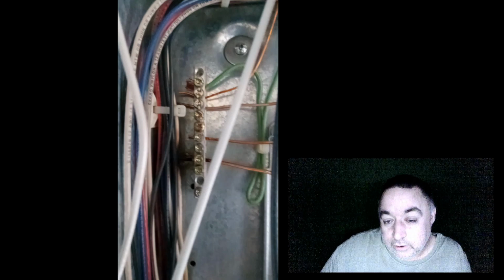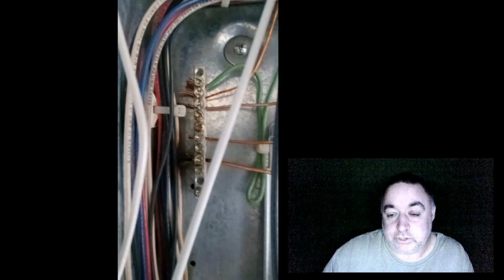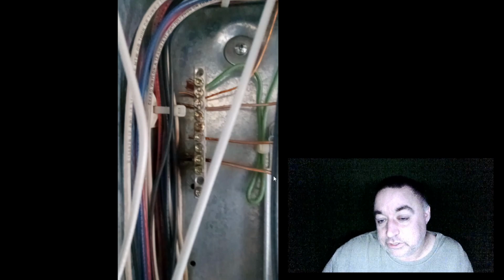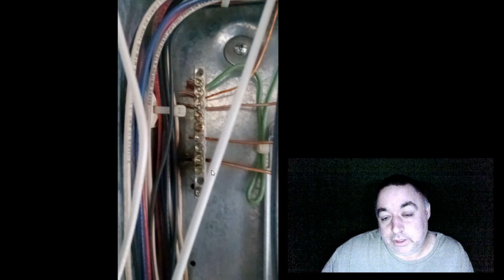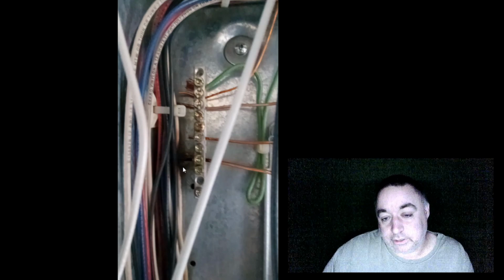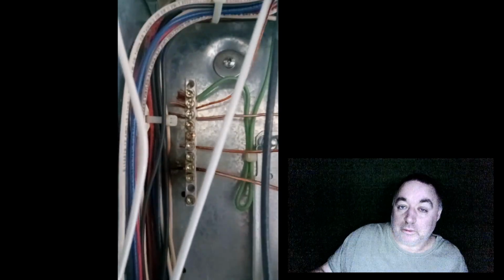But whatever is using that neutral as a return is obviously drawing way too much current. I don't know if the control board was faulty. I mean, I didn't ask them too many questions. They just said the control board was bad. But this right here is definitely signs that major current is being sent back to the panel on the ground wire. To have it burn like that, to have it loose, I mean, you can tell it's been arcing for a while. So that could definitely be another problem. That's a second problem. There it is. So, look at that. Look at that black. Oh my God.